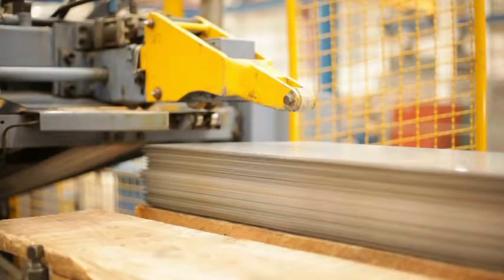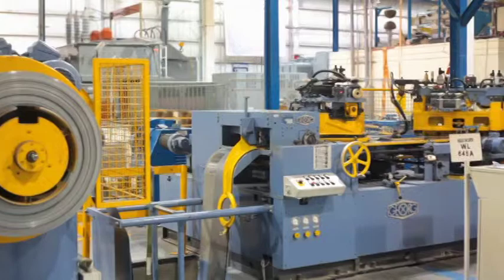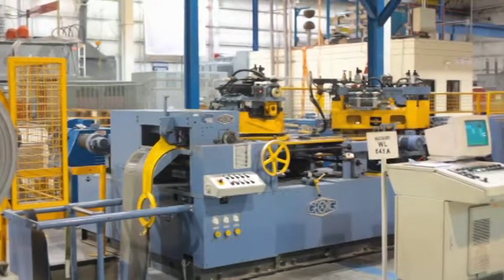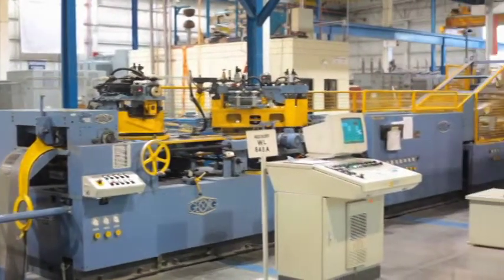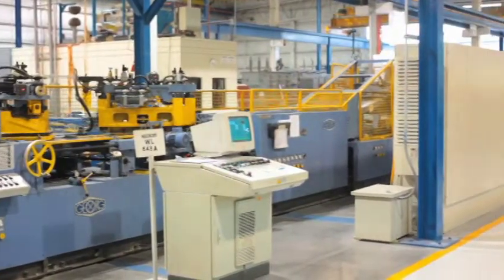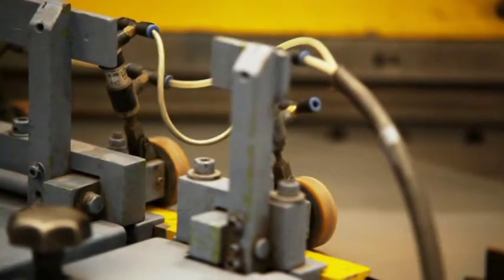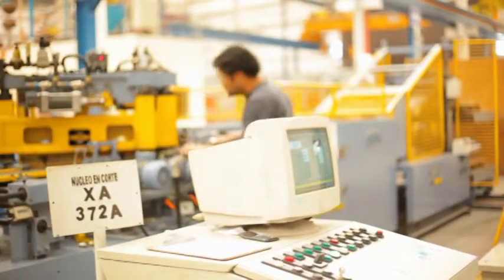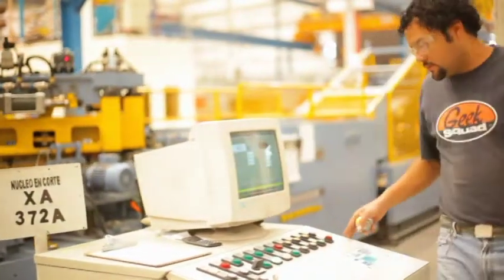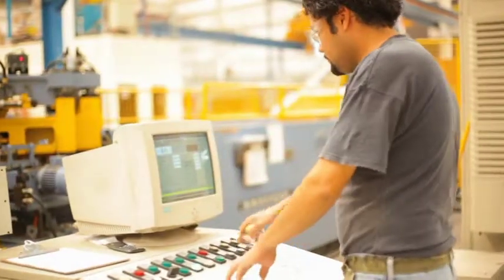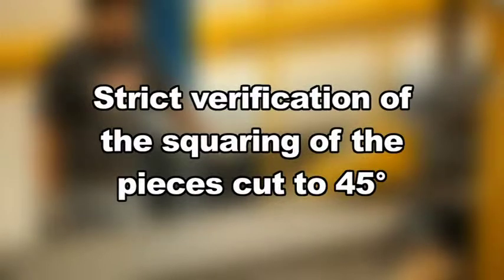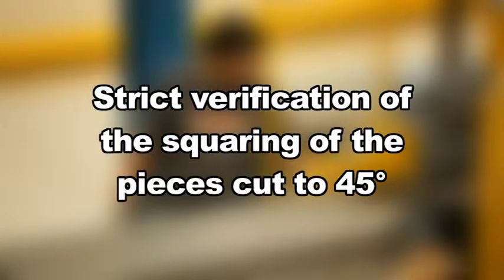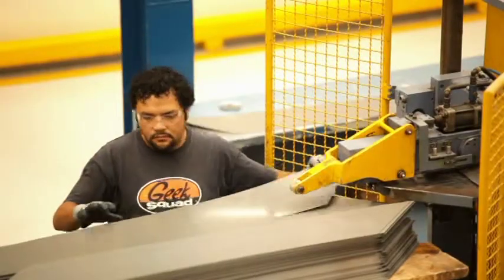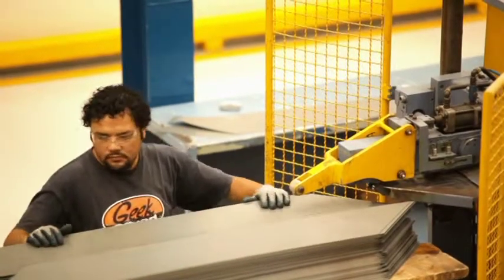Meanwhile, in the core cutting area, a precise German manufactured machine is used to cut silicon steel sheet in the most accurate and efficient way, by not allowing variations or burrs in the cut. The most common steels used here are the M3 and M6 with a miter type cut setting, and if necessary, we can bring from our sister plant's step lap core cut steel. The inspection in this process focuses on strict verification of the squaring of the pieces cut to 45 degrees, as well as the repeatability in the length of such parts.